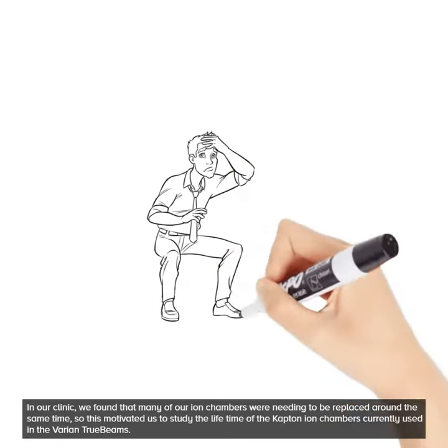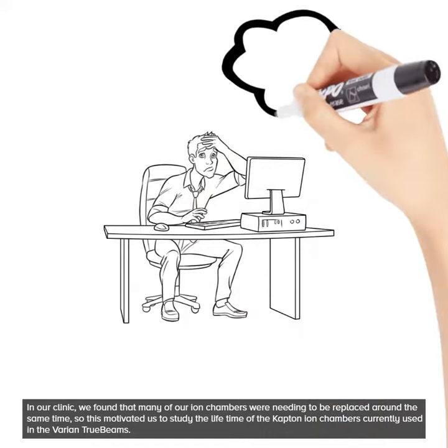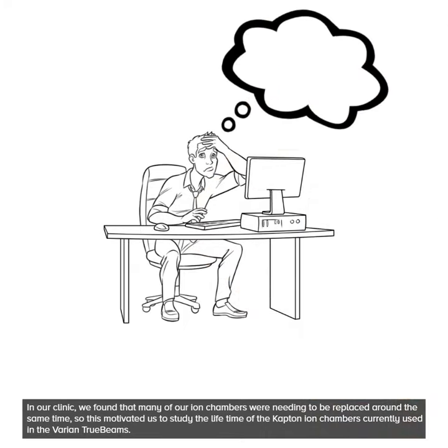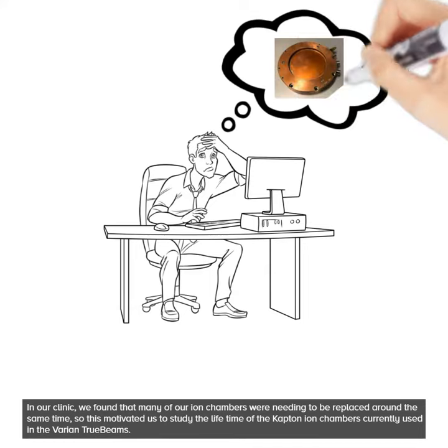In our clinic, we found that many of our ion chambers were needing to be replaced around the same time, so this motivated us to study the lifetime of the Kapton ion chambers currently being used in the Varian TrueBeams.